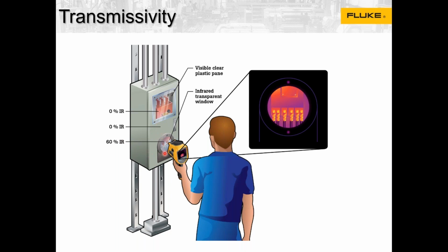But if you are using an IR window, because we are using a special glass called germanium, this germanium glass can transmit energy. So you just need to set up your camera to 60% transmission. Depending on the IR window, you will see the transmission percentage on its data sheet, or you can make a simple test to check the transmissivity of your IR window.